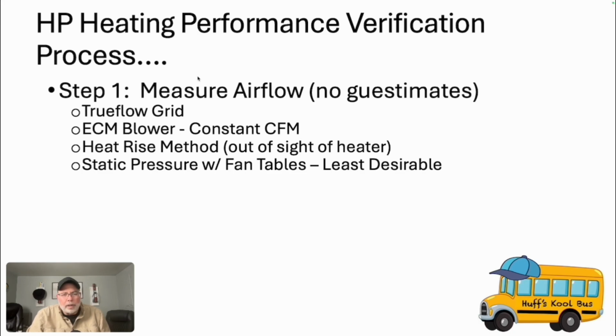Some people will say, hey, I can use static pressure with my fan tables. Well, that's actually the least desirable. Now, I know what you're thinking. Aren't we telling people that they should be checking static pressure on every job? Absolutely. We should, every service call, we should measure static pressure. In that way, we know how restrictive the duct system is.